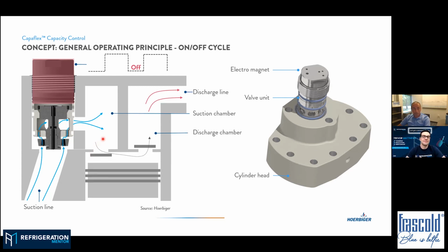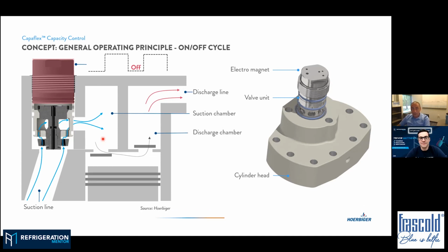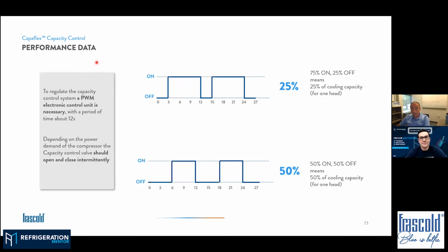So very similar to what we were using on the fluorinated refrigerant. The main difference, let's say, is on the control side. So on the control side, we would use a PWM controller for this type of system. The main reason is to keep the cycle in a period usually of about 12 seconds. I think we understand why.